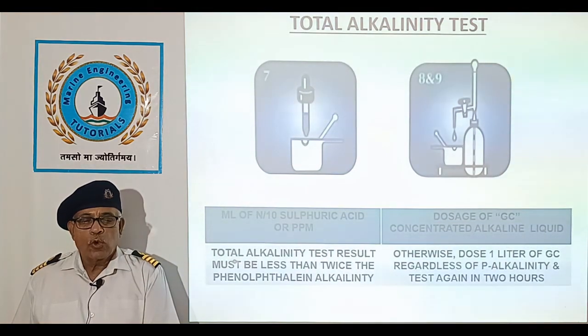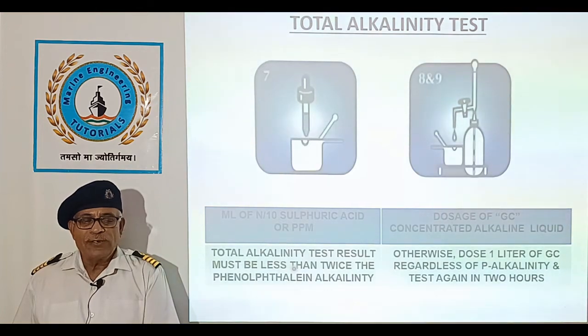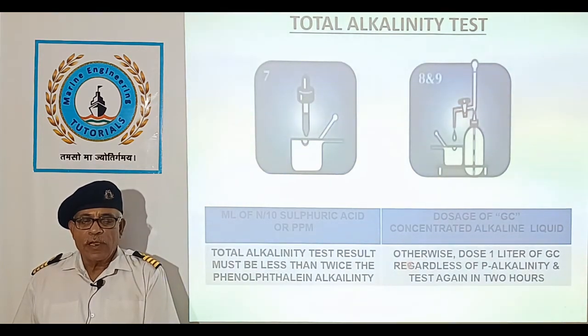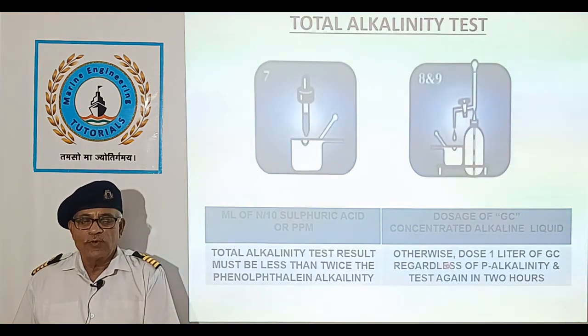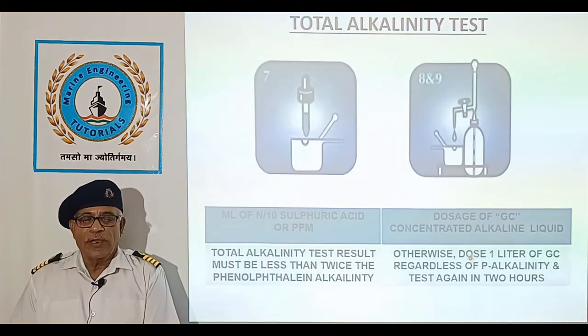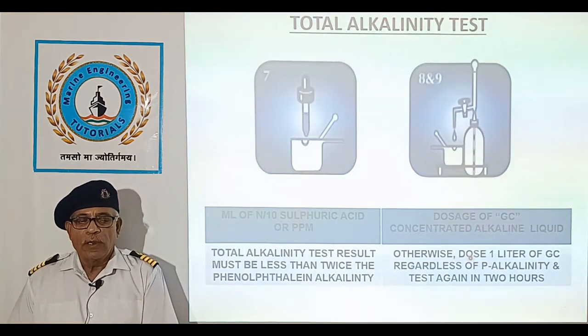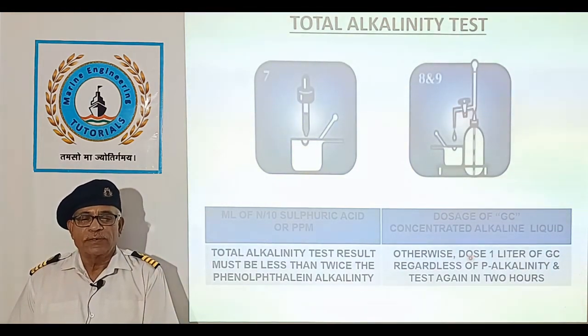Total alkalinity test result must be less than twice the phenol alkalinity. In case it goes more, dose 1 litre of GC regardless of P-alkalinity and test again in 2 hours.